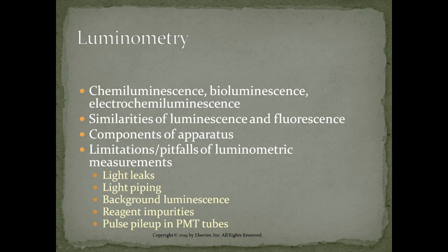There are limitations to it, but it's used a lot in chemistry analyzers. There are times, like when an analyzer doesn't have the light source locked down, you have leaks in with light, which inhibit and give you problems with determining quantities and the existence of it. But it is definitely a commonly used process.